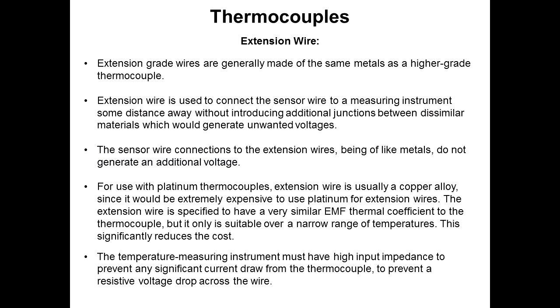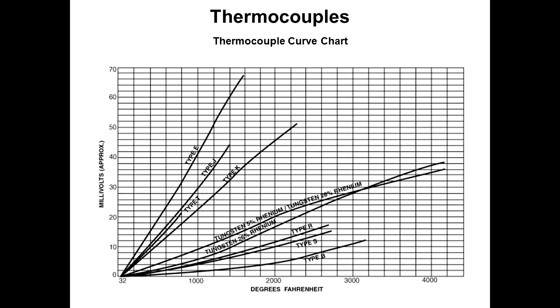The temperature measuring instrument must have a high input impedance to prevent any significant current draw from the thermocouple, to prevent a resistive voltage drop across the wire. You don't want the instrument pulling from your thermocouple voltage. You want it just reading it. Different thermocouples have different curves, but they're all basically an S-shaped curve to one extent or another, so they're not linear. You need to have a microprocessor to linearize them for best accuracy, to straighten out that curve so you'll get the same accuracy up and down the scale.